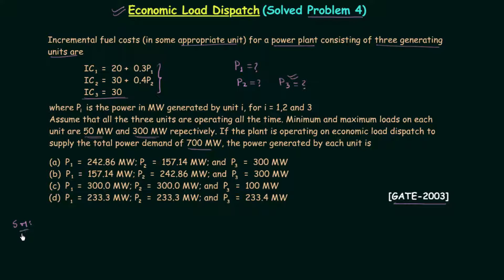From the lecture on economic load dispatch, if the incremental cost is constant we always load that particular generator the most. Here IC3 equals 30, meaning the incremental cost of the third generator does not change with power. So we will load the third generator to its maximum of 300 megawatt.